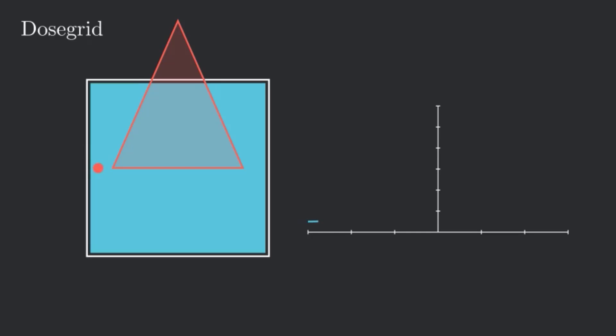Let's review how we measure beam profiles. Here we have an idealized water tank and a detector moving across a radiation beam. And we can see, generally, there's a flat region, and then we have penumbra.